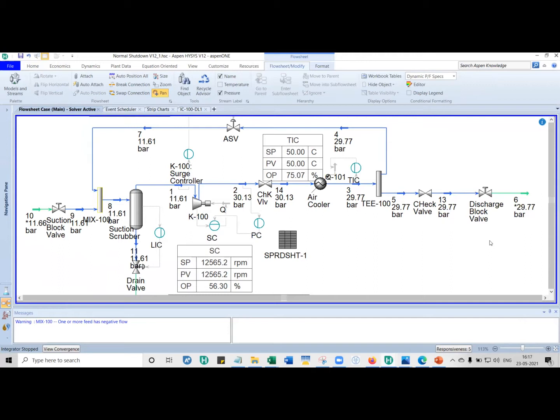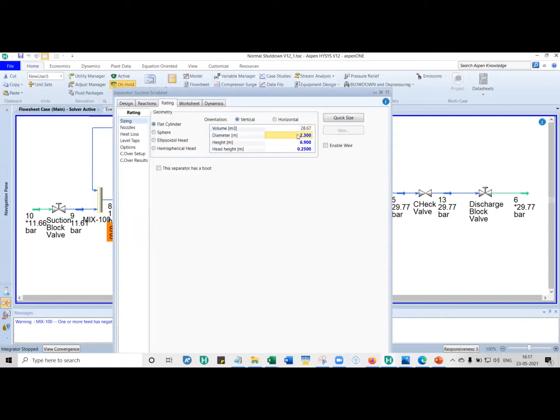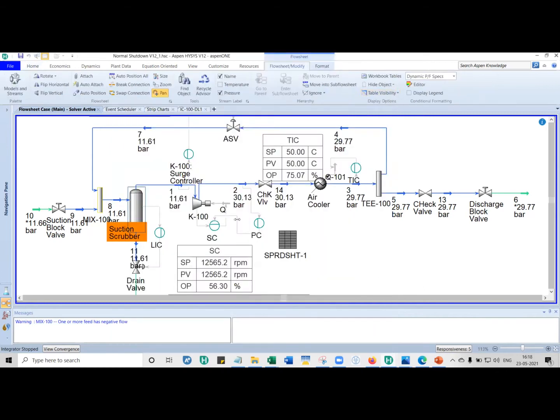So this is a normal shutdown case. When you build a compressor model, the kind of information you need is: one, you need to have your equipment volumes. Remember, in HYSYS what it is actually doing is that it is only a thermodynamic solver — it is only interested in the volumes. You can put pipes which it will do the hydraulics, but for dynamic simulation analysis it's the volumes which really matter. When you give your diameter and height, and do your equipment sizing and line sizing, the value actually going into the simulation is the volume — in this case 28.67 cubic meters.